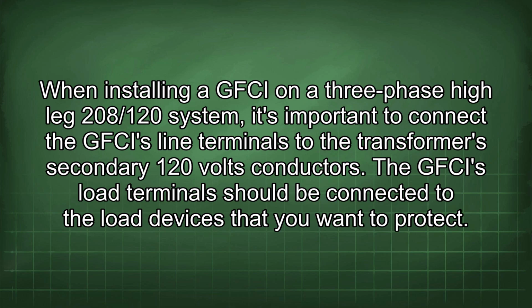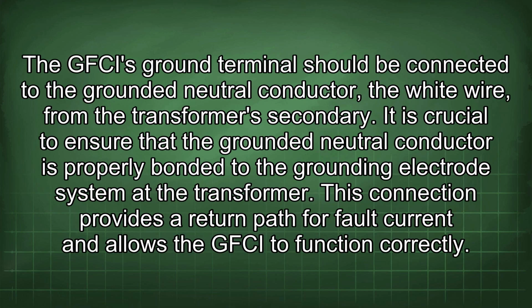When installing a GFCI on a three-phase high-leg 208/120 system, it's important to connect the GFCI's line terminals to the transformer's secondary 120 volt conductors. The GFCI's load terminals should be connected to the load devices that you want to protect. The GFCI's ground terminal should be connected to the grounded neutral conductor, the white wire, from the transformer's secondary. It is crucial to ensure that the grounded neutral conductor is properly bonded to the grounding electrode system at the transformer. This connection provides a return path for fault current and allows the GFCI to function correctly.